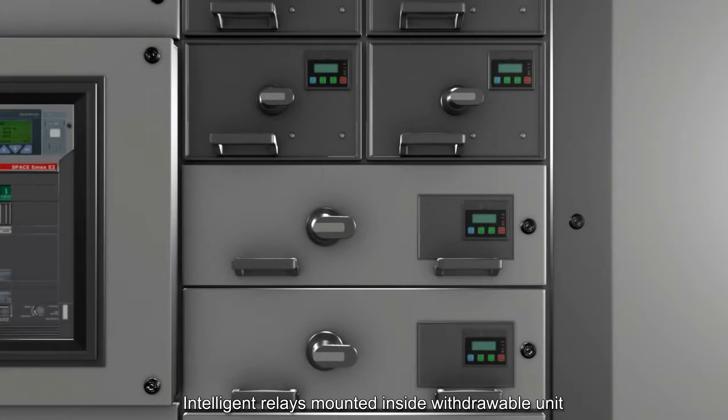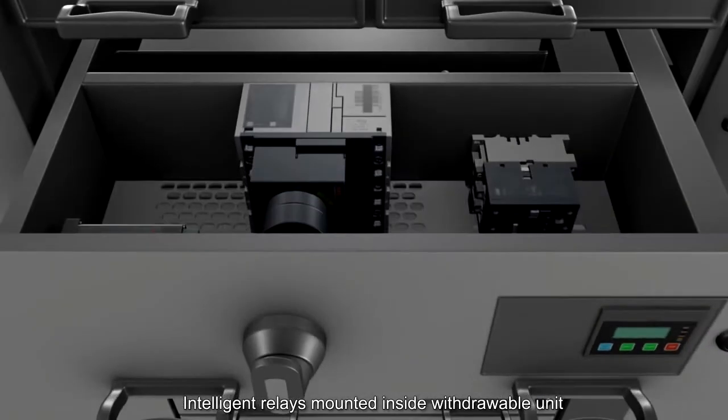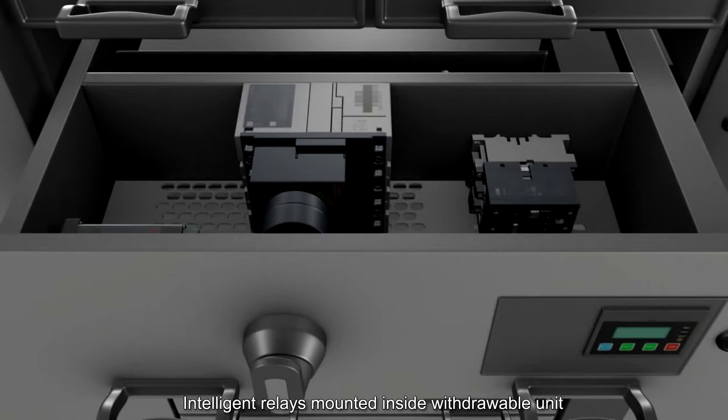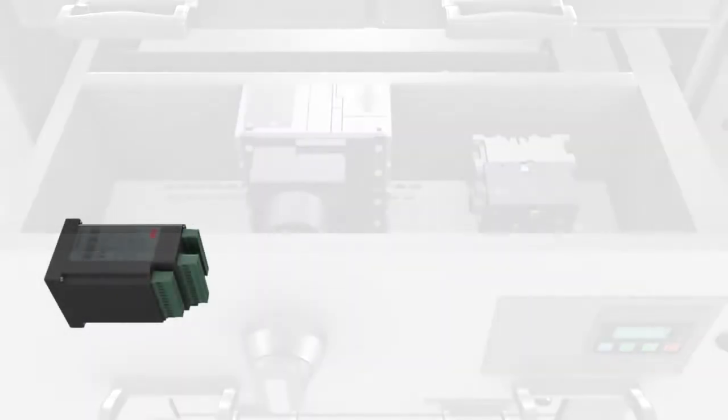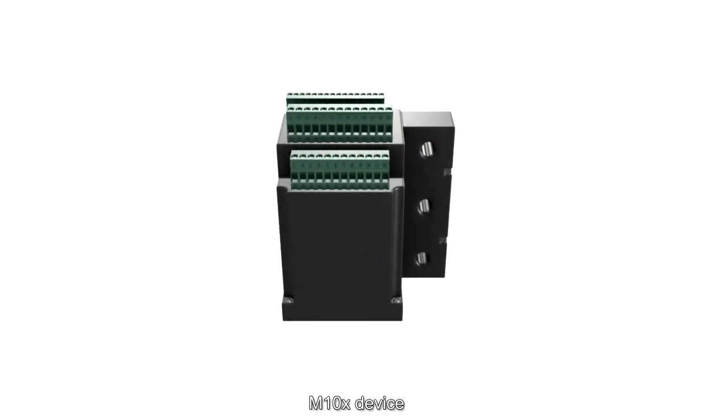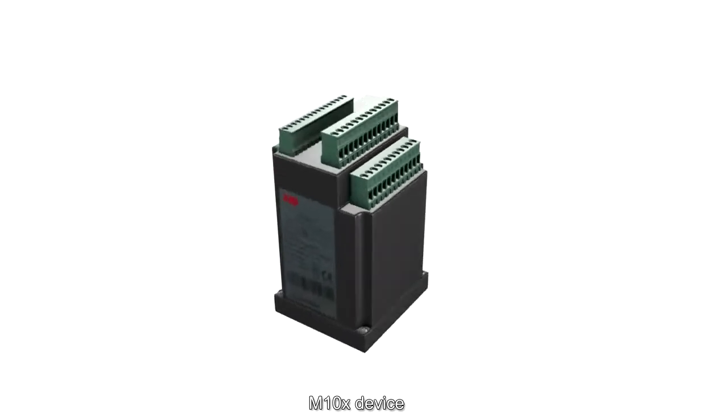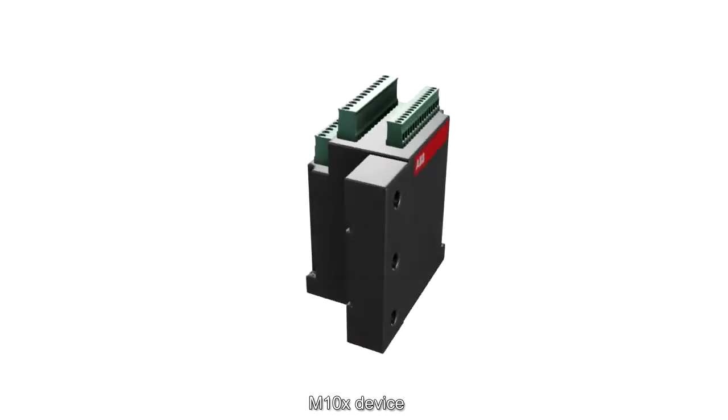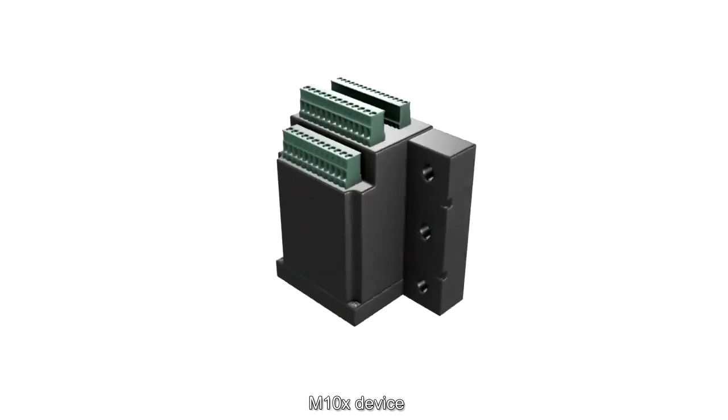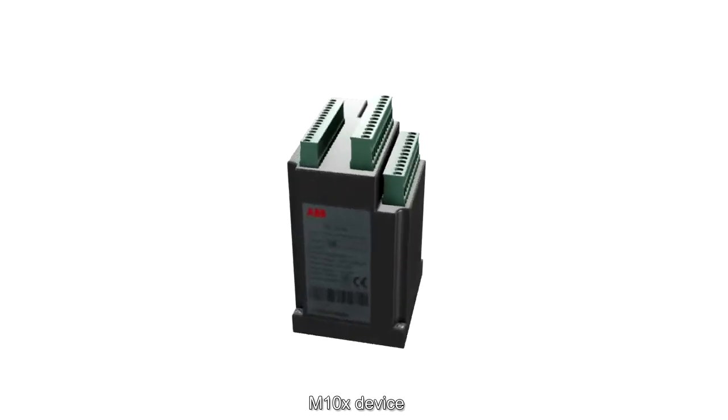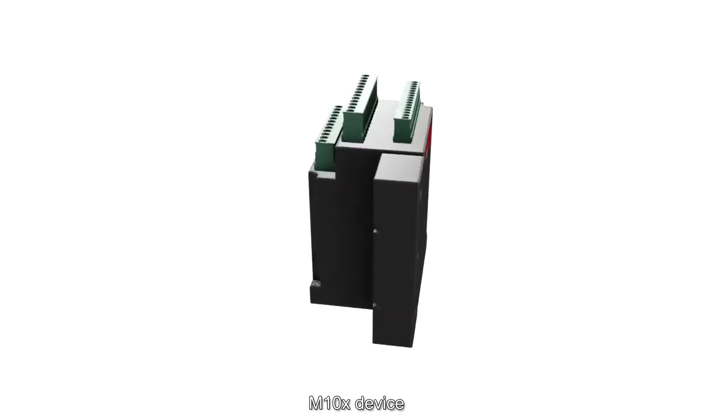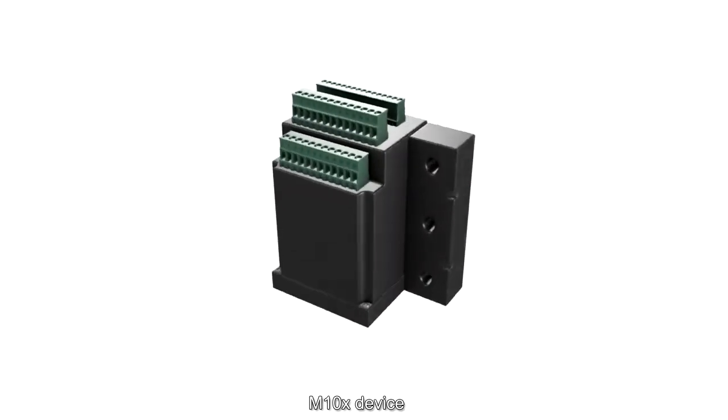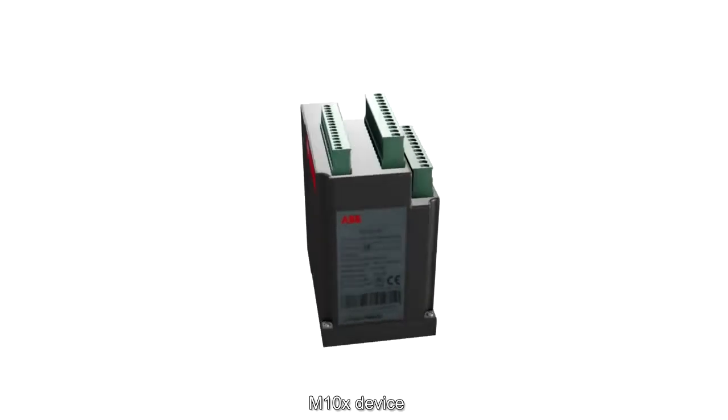ABB's M10X series is an intelligent relay which provides protection functions including thermal overload, current unbalance, under-voltage, and earth fault protection. It is suitable for typical electrical functions such as direct online or reversion motor starters, star delta or two-speed motors, or even for feeder monitoring.